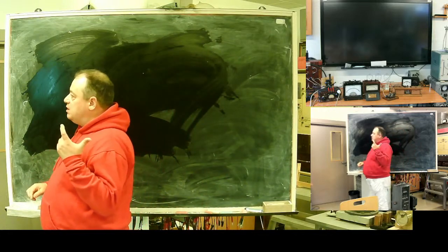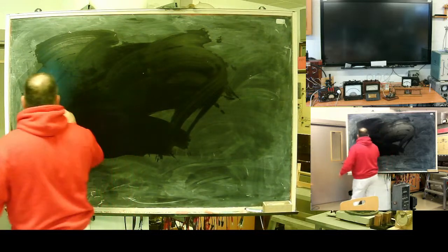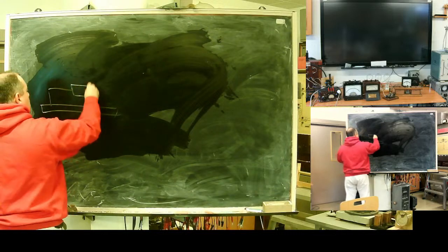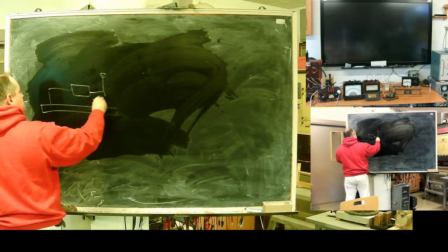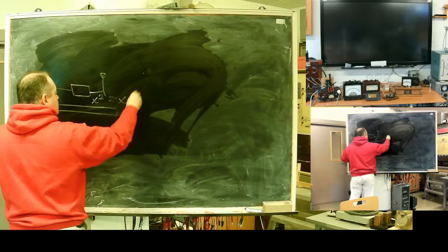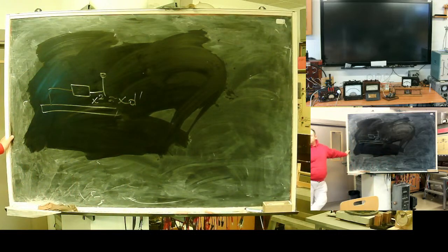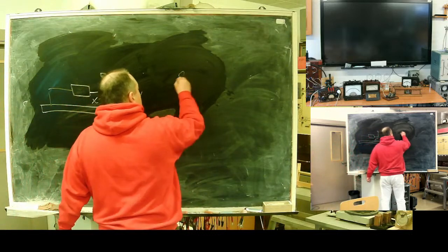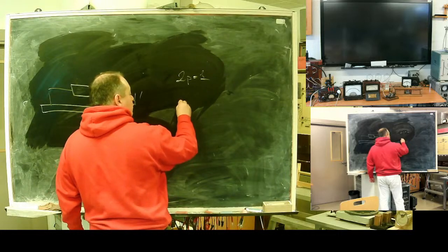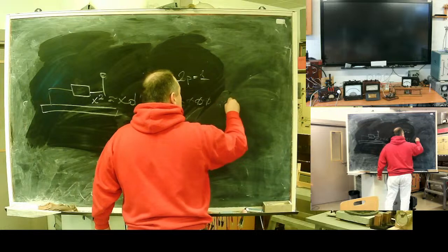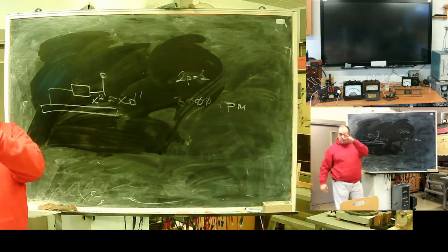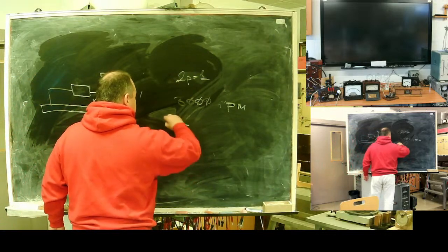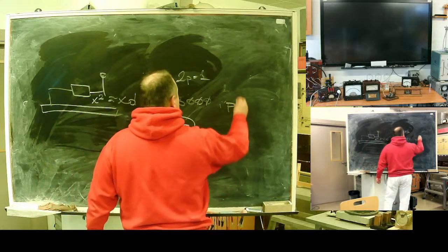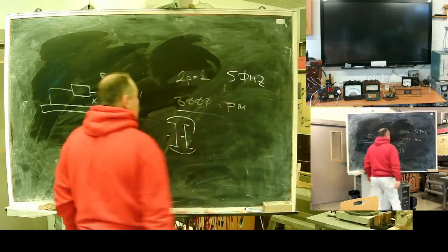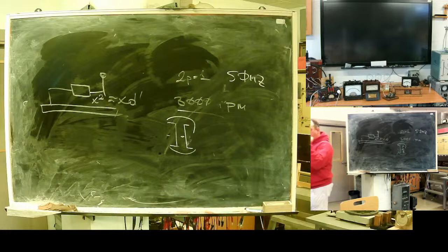What about negative sequence? For negative sequence, it's something like this. Negative sequence reactance is approximately subtransient. What about negative sequence? The generator rotates forward with synchronous speed. So for one rotation speed, what will it be? 3000 RPM. Yes? Simple. For a generator with 50 hertz, we will have 3000 RPM. It's the rotation speed for direct sequence.